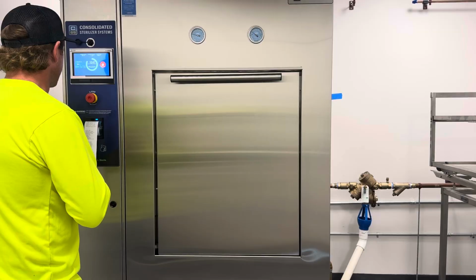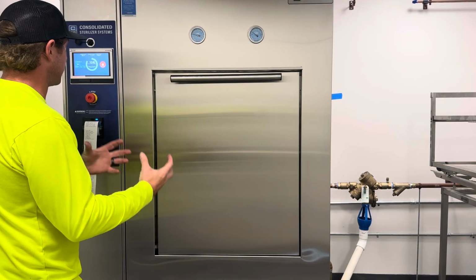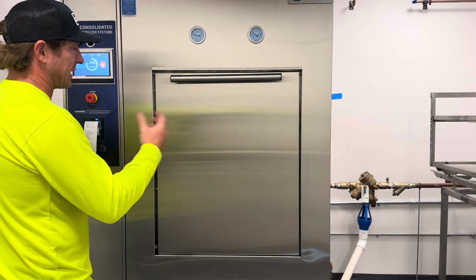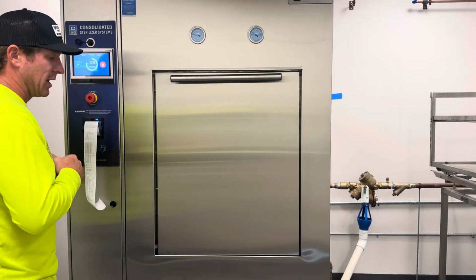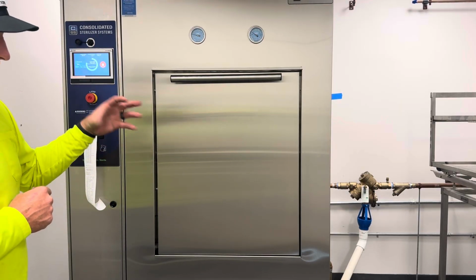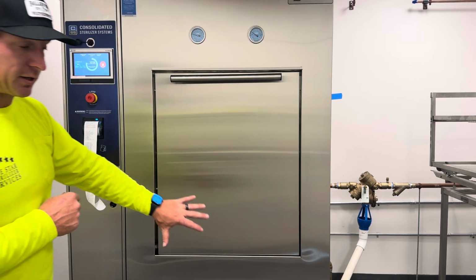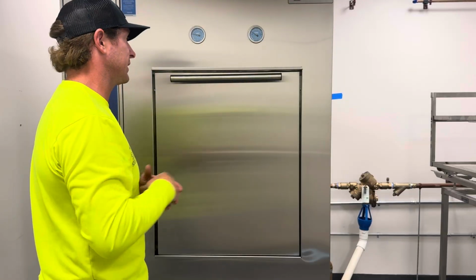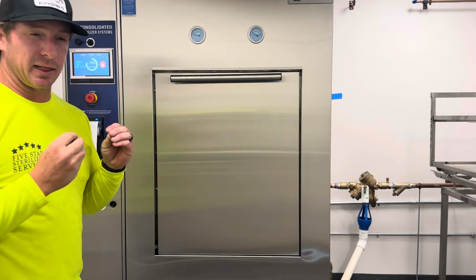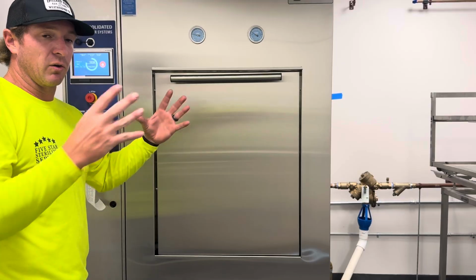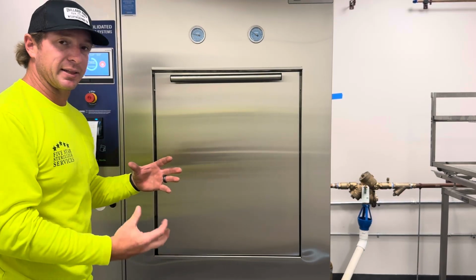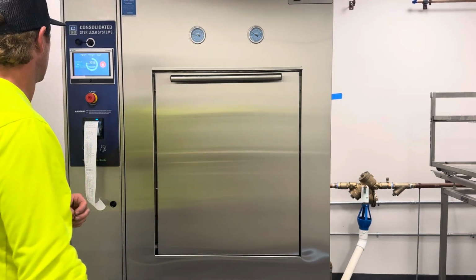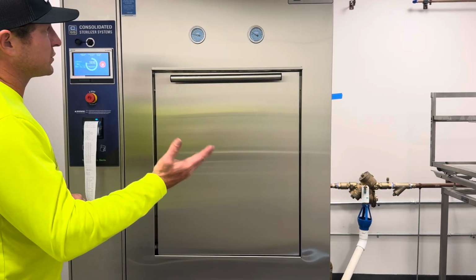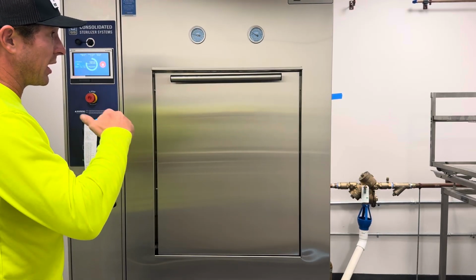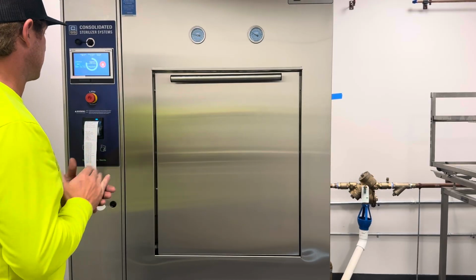We're at 105 degrees as the generator's generating more steam to put back into the chamber and also the jacket. You can see this machine, because we're generating our own steam underneath locally instead of a greater steam supply like within the building, it's going to take a little bit longer to run an overall cycle just because we're having to generate the steam as we're using it. But it's coming up, so it may drop in temperature until it kind of bottoms out, and then it'll slowly start rising up.